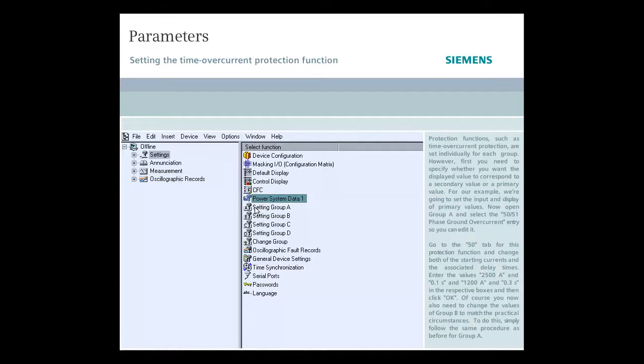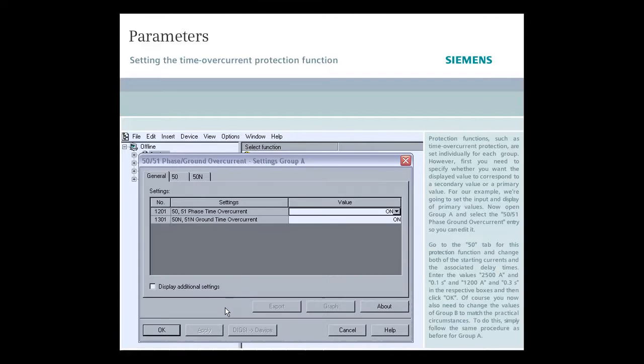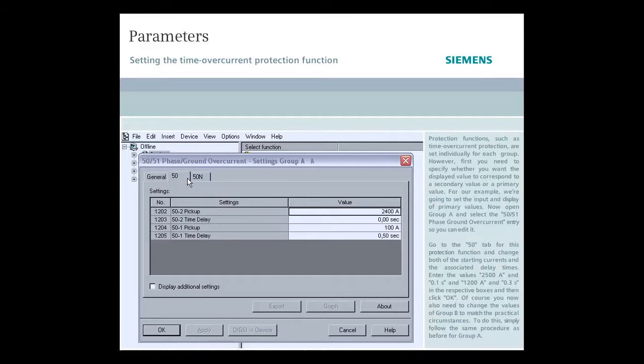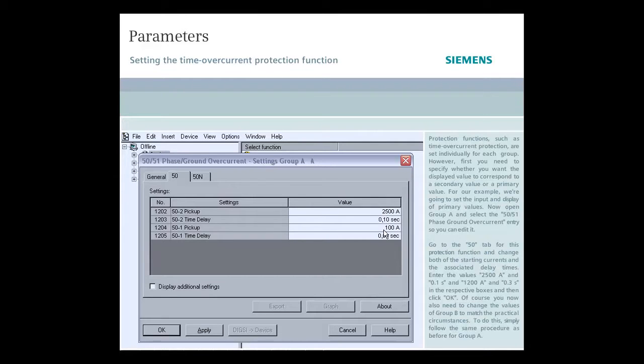Now open group A and select the 50-51 phase ground over current entry so you can edit it. Go to the 50 tab for this protection function and change both of the starting currents and the associated delay times. Enter the values 2500 amperes and 0.1 seconds and 1200 amperes and 0.3 seconds in the respective boxes and then click OK.